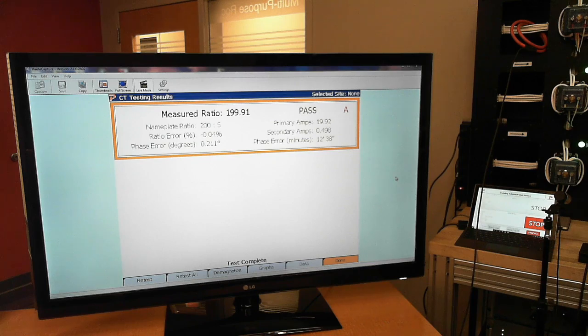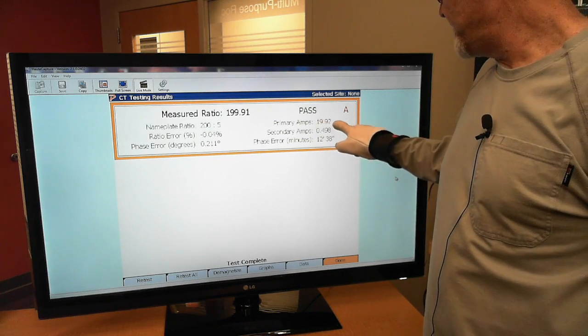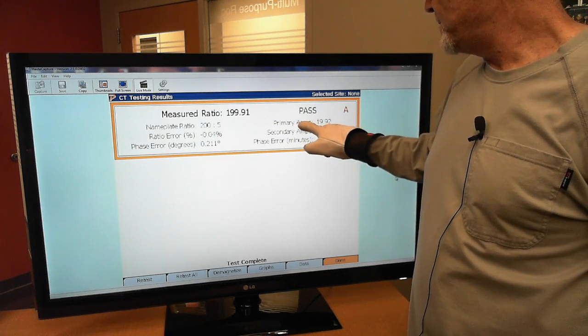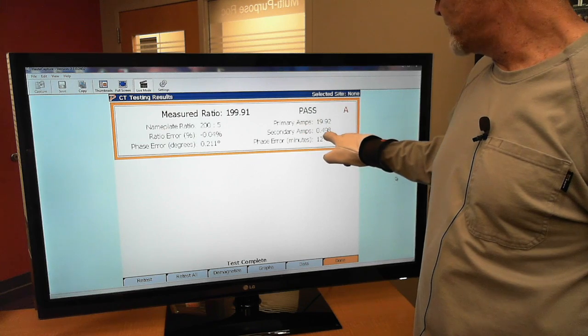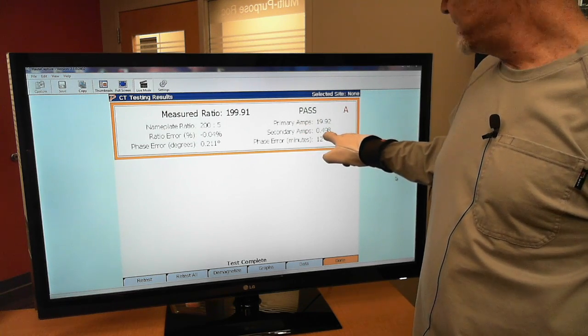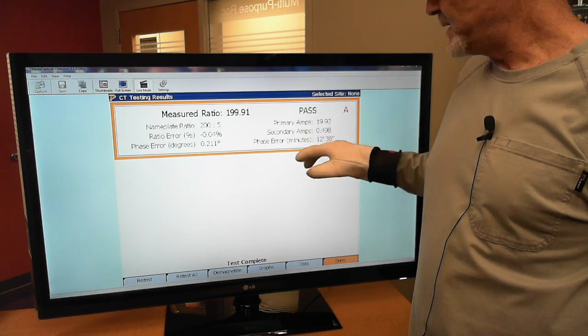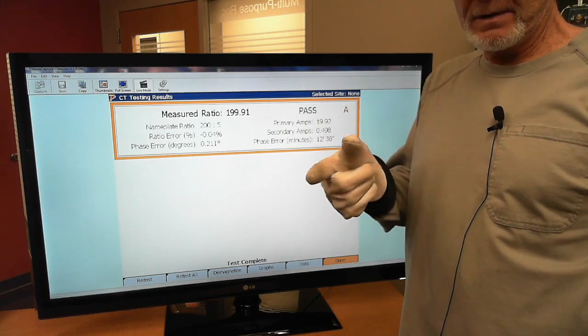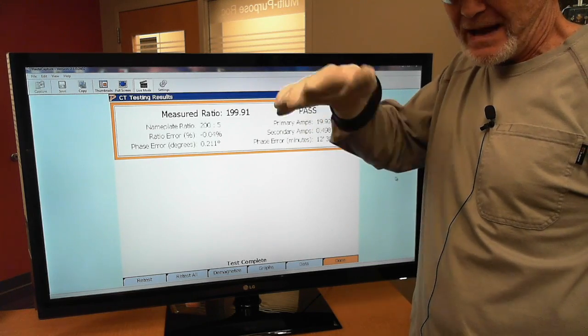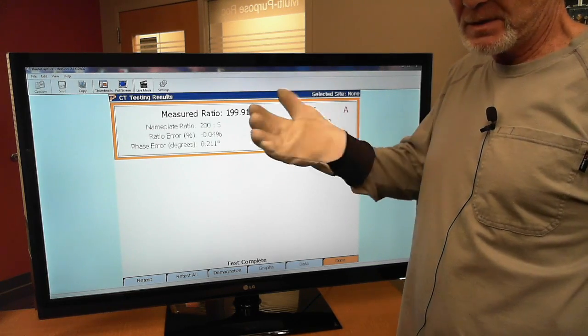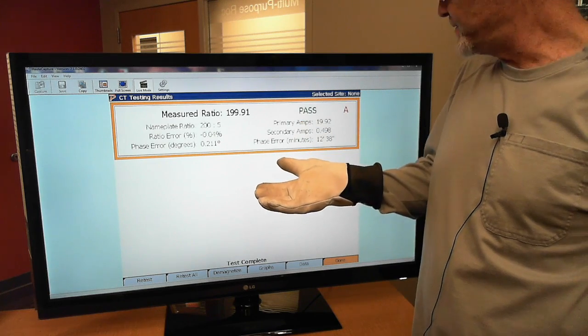So it did what we asked it to do. It put the 20 amps through there. It then measured on the secondary side and came out awful darn close to 5, didn't it? And we said, 0.5 — excuse me, so it came awful close to a half, which is what we were looking for, right? Because we always say 0.5 is that number that we look for. If we don't have at least 0.5, it's going to be tough to test.